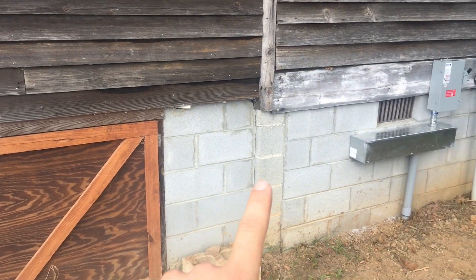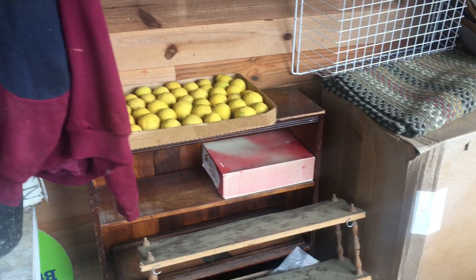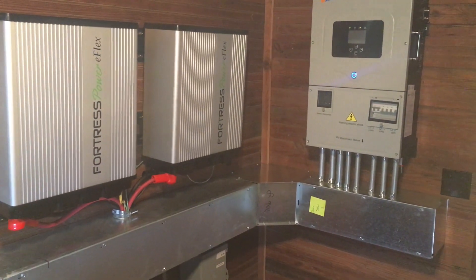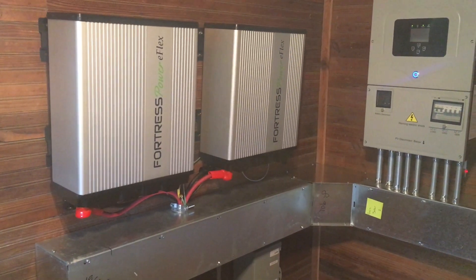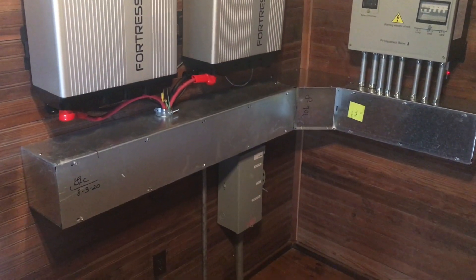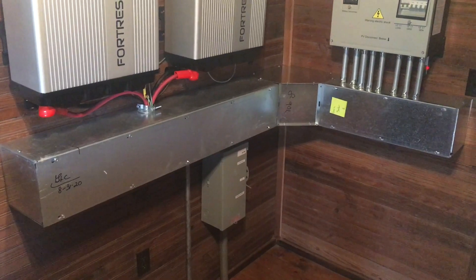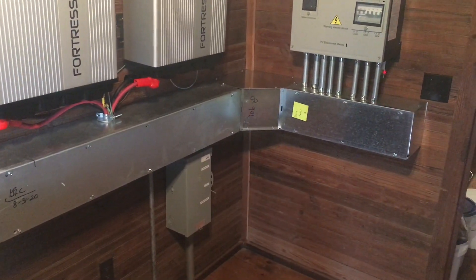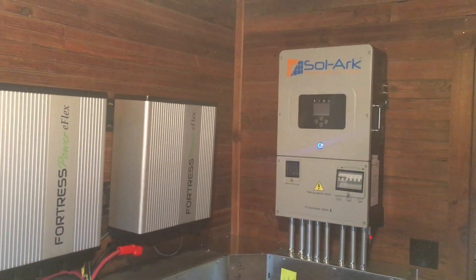Underneath the house in the crawl space it goes all the way to the other side of the house where our solar mech room is. In here among these rustic settings we have our solar system with our two batteries — these are Fortress eFlex 5.4s. They're brand-new lithium ferrophosphate batteries from Fortress, paralleled. Down below that's our transfer switch, which we use as a bypass on every system so the customer can bypass the Sol-Ark and instantly have grid power passing through to all their loads.